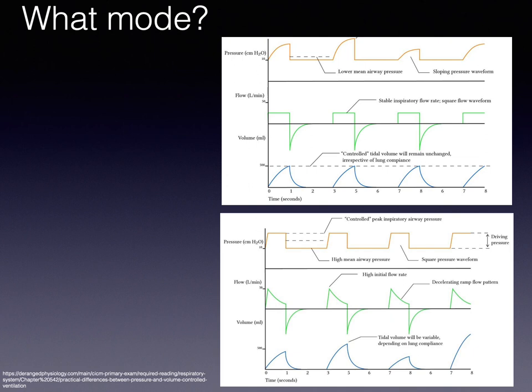You will see a common screen on the ventilator with a pressure curve, a flow curve, and a volume curve. To know which mode it is, look at what parameter is flat. For example, if the flow is flat, it means during the inspiratory cycle the flow was constant — this is volume AC. On the bottom graph, if the pressure is flat during the inspiratory cycle, this is pressure assist control. The tip is to identify which parameter is constant — which parameter is flat on the curve.